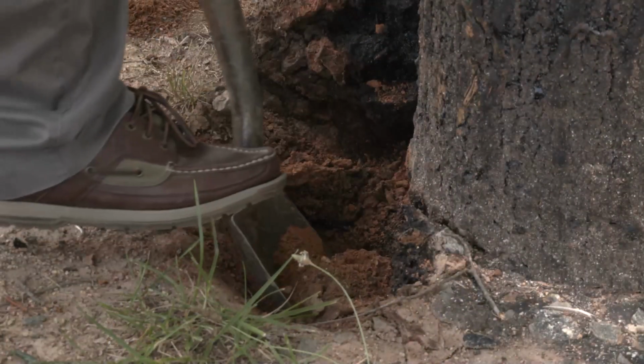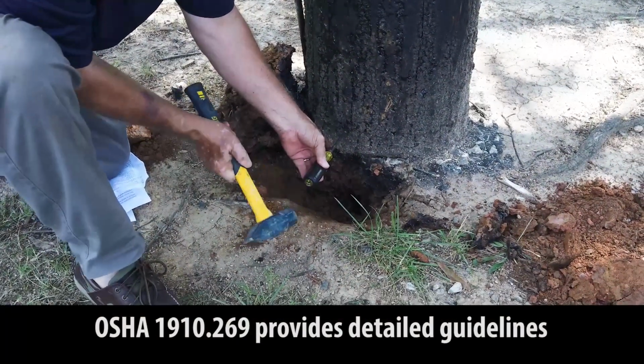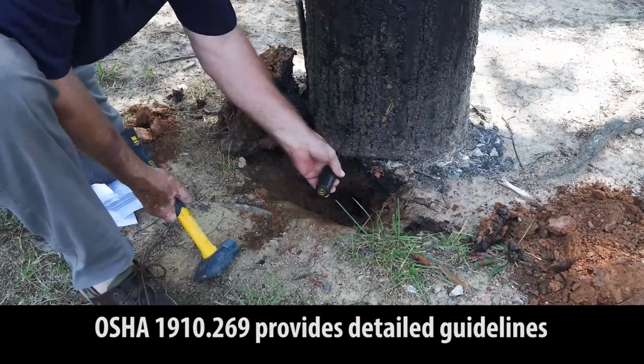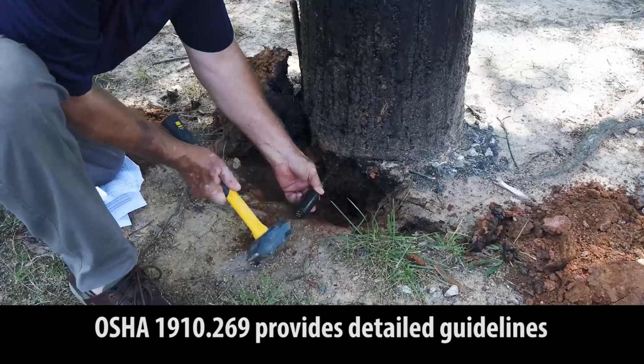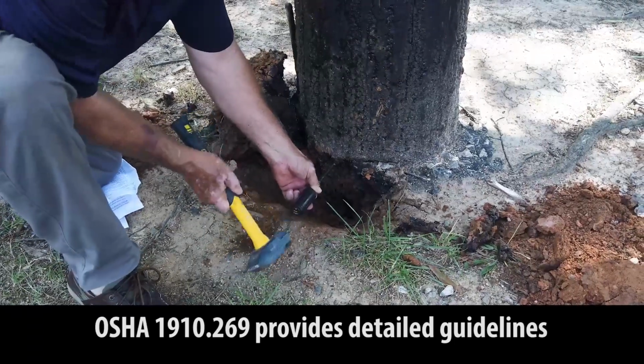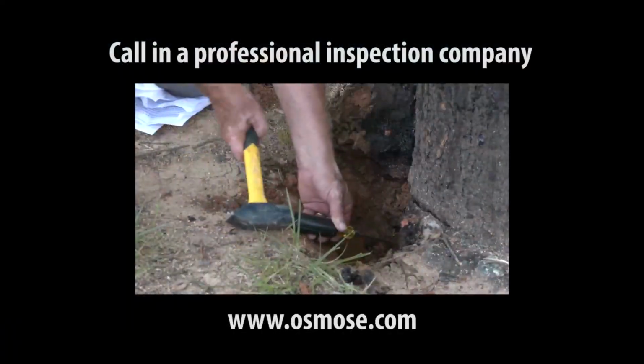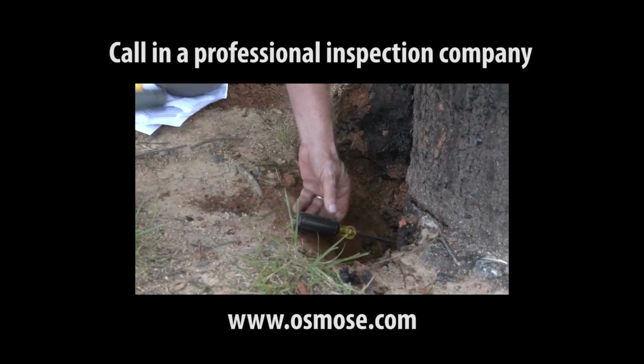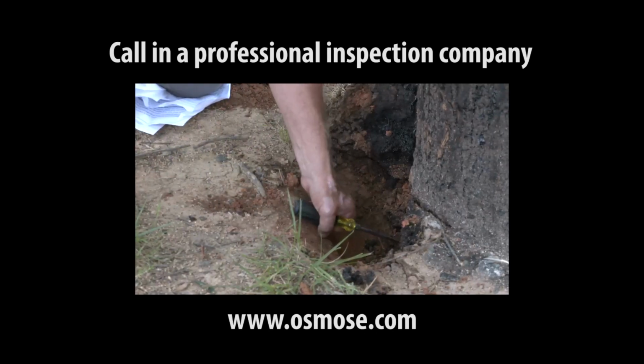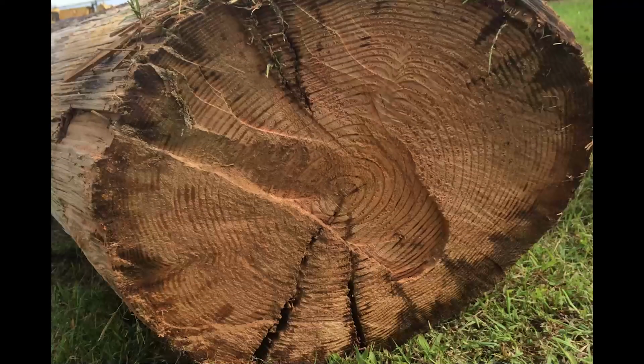Once you check for leaning, twisting, or cracking, move on to the condition of the wood pole itself by checking the base of the pole for deterioration. To do this, drive a screwdriver into the base of the pole at ground level. This is the area of the wood pole most susceptible to decay and stress from the wind, so you want to check to see if there are any signs of rotting or deterioration. If you are unsure about the results you're seeing, consider bringing in a third-party professional to conduct further testing and provide a full report on the condition of your wood poles.